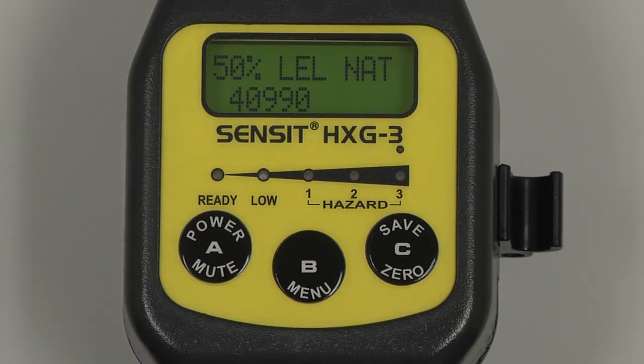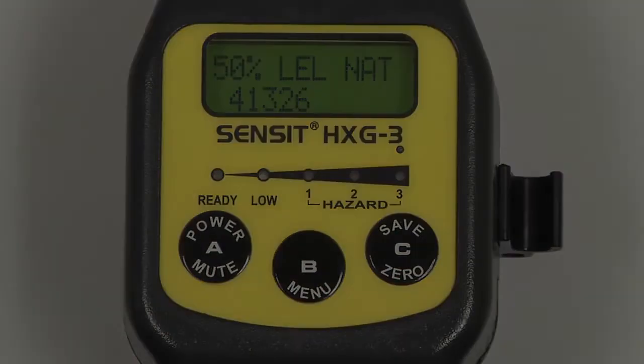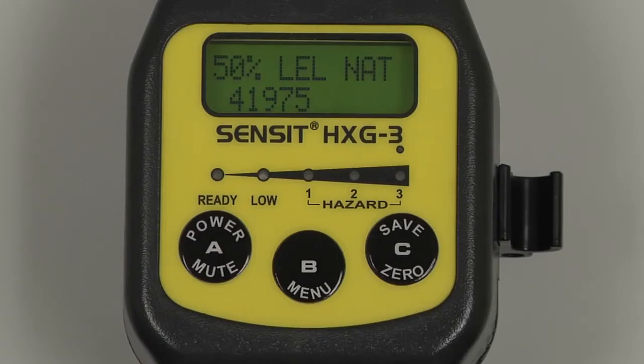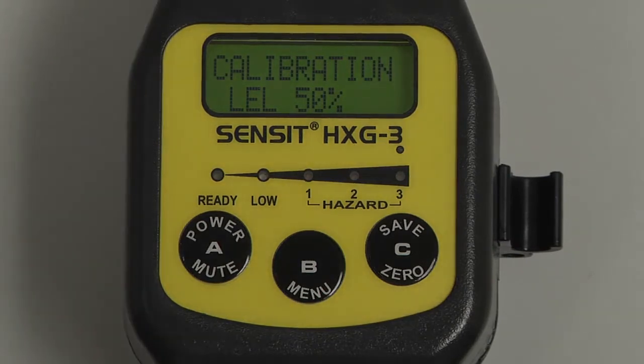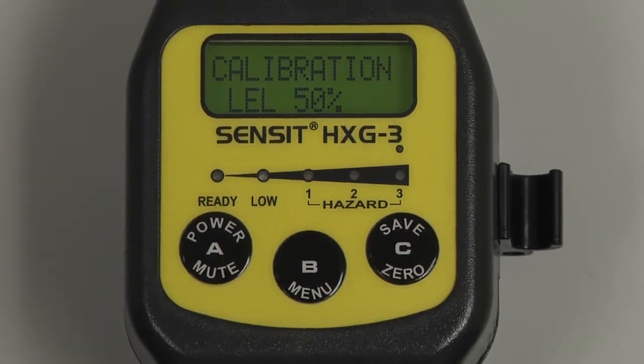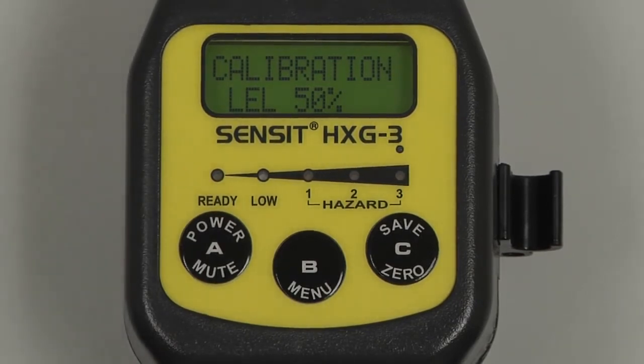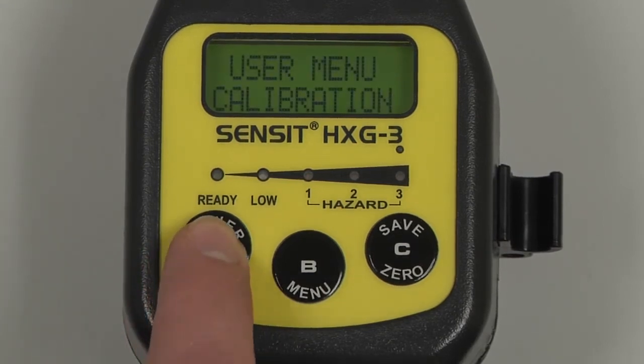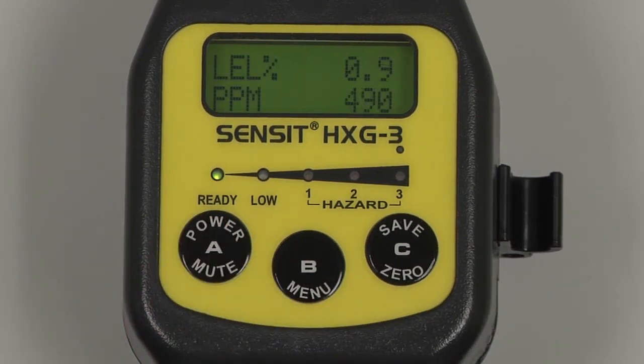Once a stable reading has been achieved, data saved will be displayed, and the calibration will be complete. The data was saved and the calibration is complete. We can now turn off our regulator and remove the cal adapter from the end of the gooseneck, and return back to the user menu and then the working display by pressing and releasing the A button. Allow the instrument to clear before powering off.